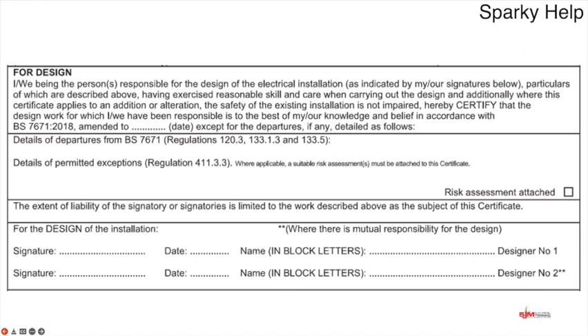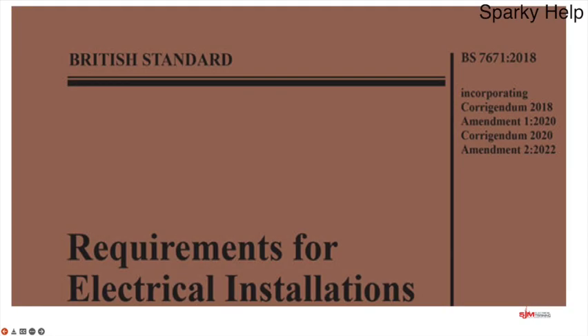Well, there's a little bit at the very beginning. It says you're going to certify that the work, to the best of your knowledge, is in accordance with BS 7671, and this particular one is 2018, amended to the correct date. Now obviously it depends what amendment you're working to, and obviously there's a new one about to come out and we shall see what the outcome is on that. But whichever version you've gone to, on here we can see that it is Amendment 2, which comes out later on this year, and so 2022 is the year that goes in there.